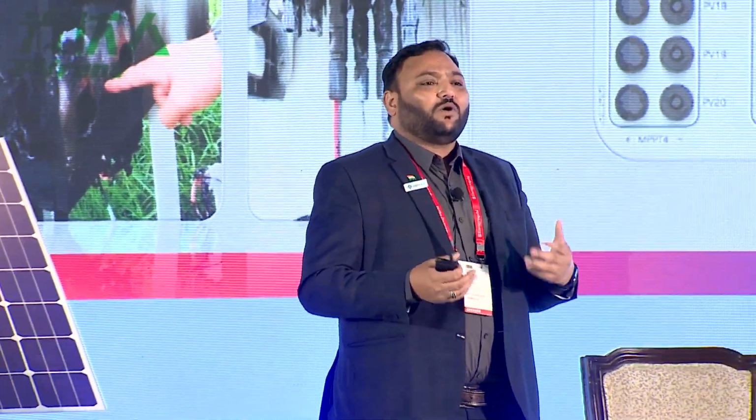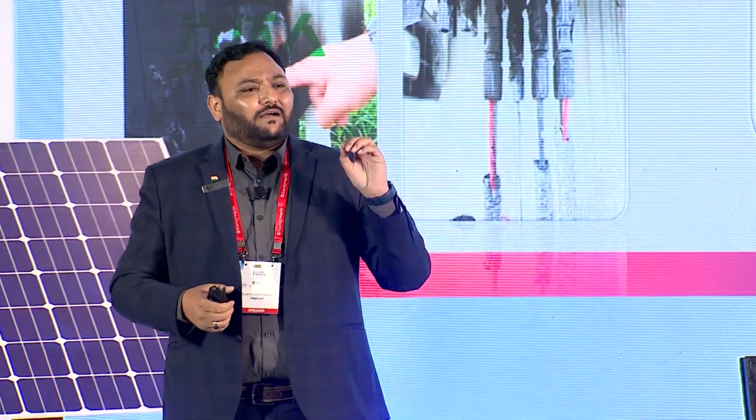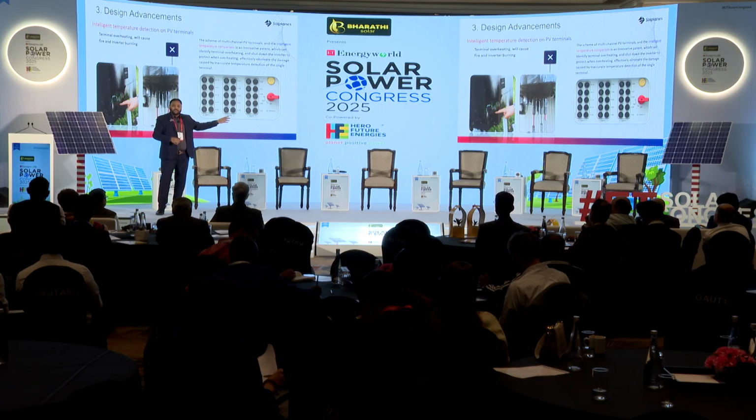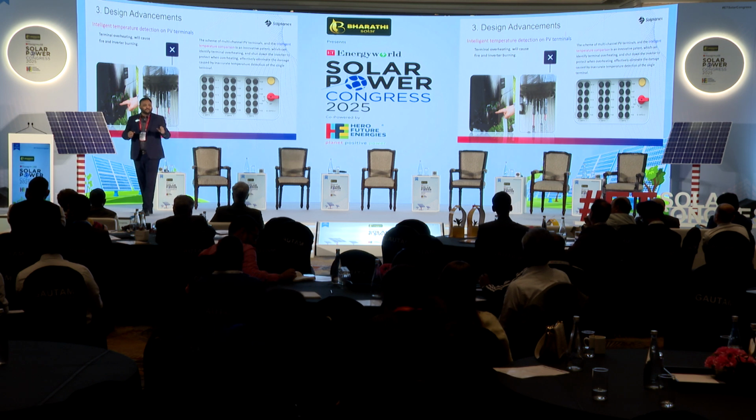To avoid such scenarios, different people have come up with different solutions. What we have done here is, at the DC connector side, we have installed sensors which can detect arcing and excessive heat, and then intelligently inform that heat is being generated. Up to here, there are different technologies that also do this. But here, along with the information, we trip the inverter automatically. We have smart DC switches built in. Those DC switches can trip immediately by themselves to prevent the hazardous situation. So these are the things we have done at the DC side.